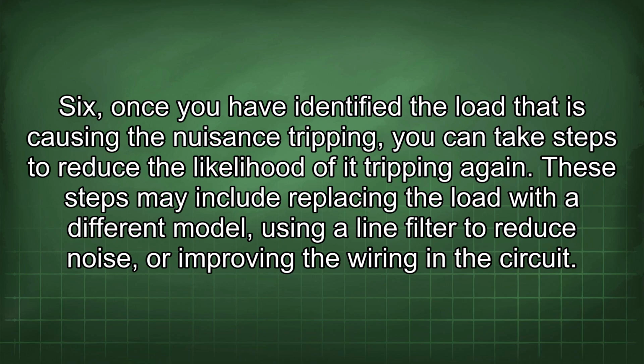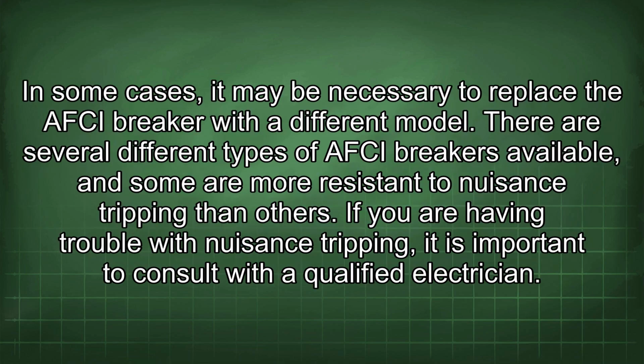6. Once you have identified the load that is causing the nuisance tripping, you can take steps to reduce the likelihood of it tripping again. These steps may include replacing the load with a different model, using a line filter to reduce noise, or improving the wiring in the circuit. In some cases, it may be necessary to replace the AFCI breaker with a different model. There are several different types of AFCI breakers available, and some are more resistant to nuisance tripping than others.